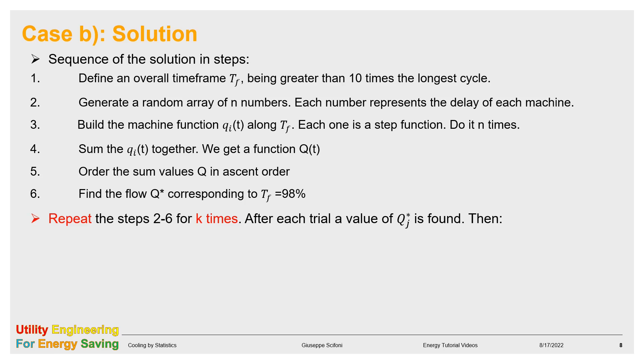When capital Q star is found, our job is still not done, because we are operating in a statistical way, and we cannot rely on one combination of cycles only. The Monte Carlo method says we need to run many trials. We repeat the steps from 2 to 6 K times, as many random arrays are generated. After each trial, a value of capital Q star is found, and eventually we calculate the average of the Q star J when J changes from 1 to K, the standard deviation, and the sum of above. The value to take for the flow needed for our equipment sizing is given at 0.9.